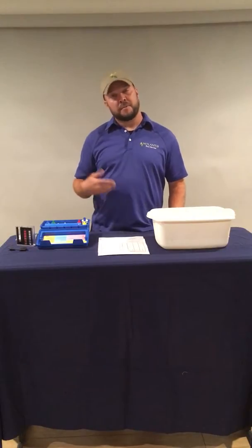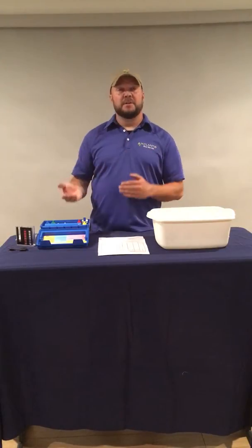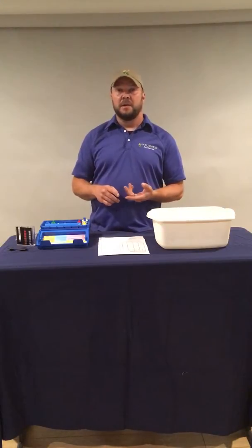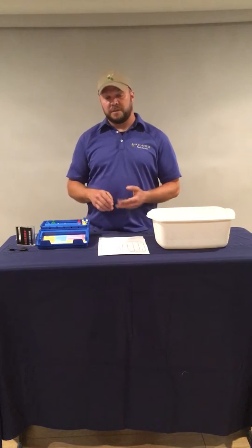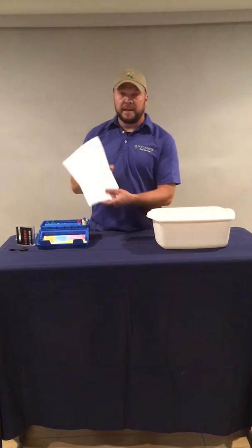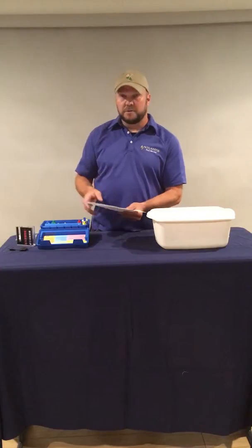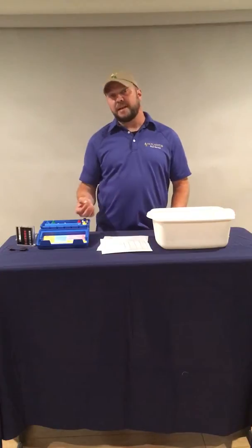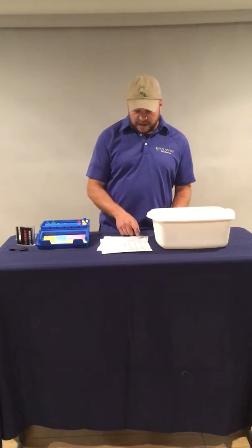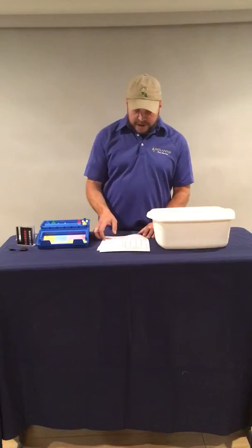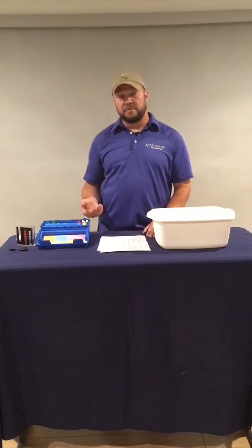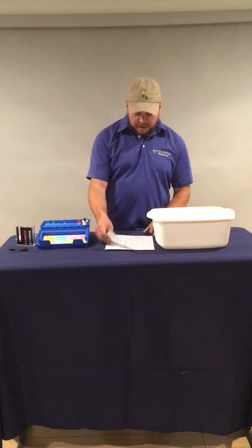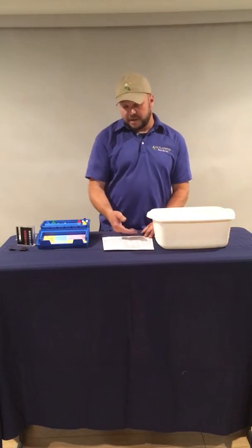Now in the state of Rhode Island, in a commercial facility, the range that you're allowed to have free chlorine in is dependent upon whether it's a pool or a spa, whether it's an indoor facility or an outdoor facility. If you check out your test logs, that we have a link to on our website, they'll show you. For an indoor pool, you can have as low as 0.7 parts per million of free chlorine and as high as 2 parts per million. In an outdoor pool, you can have from 0.7 to 3.0. In a hot tub, indoor or outdoor, it goes from 1 to 5 parts per million. And all that's on your log sheet.